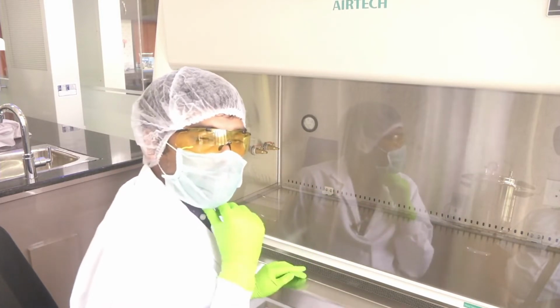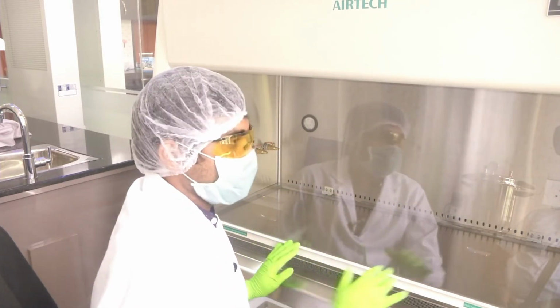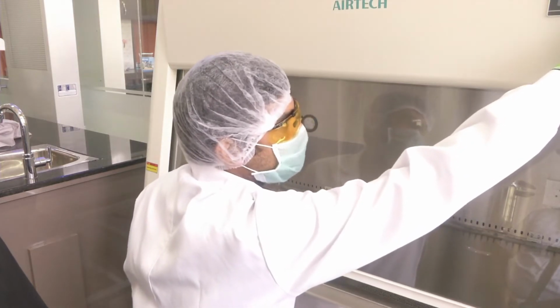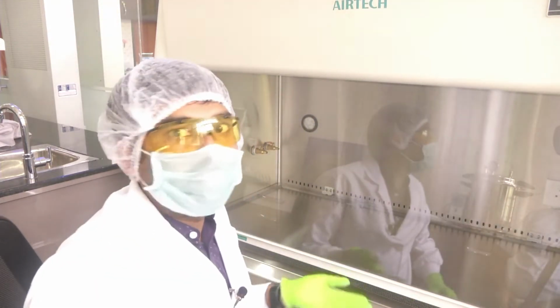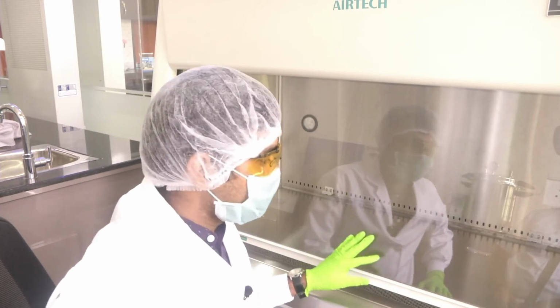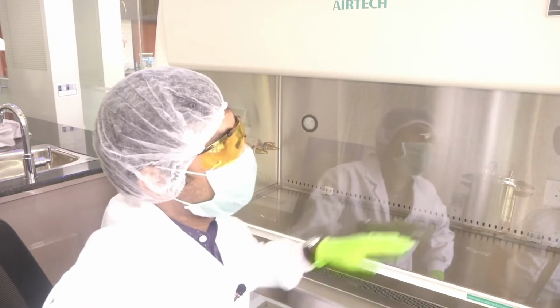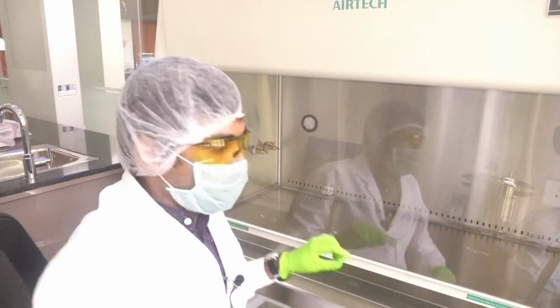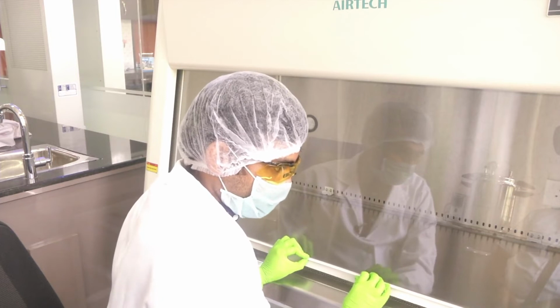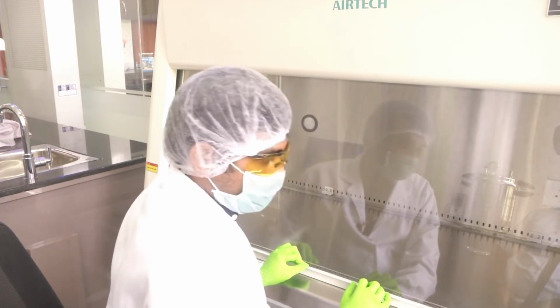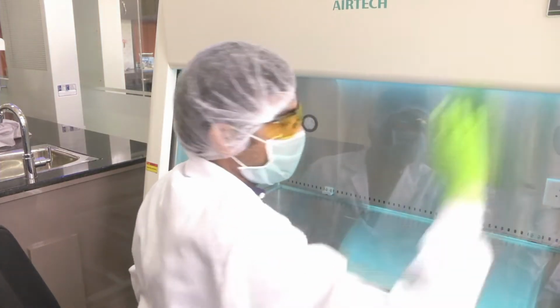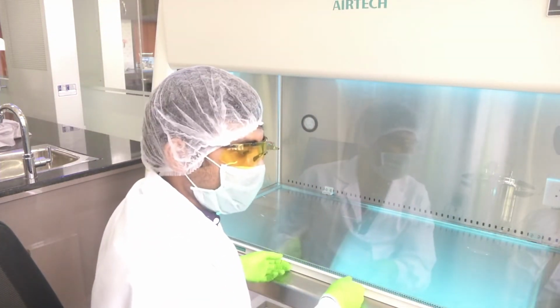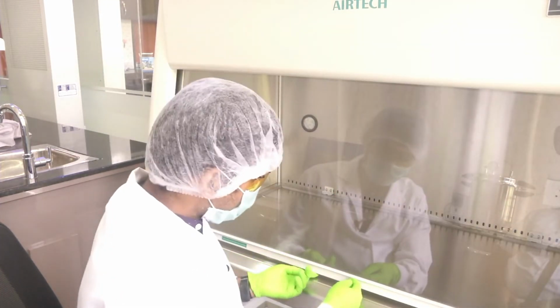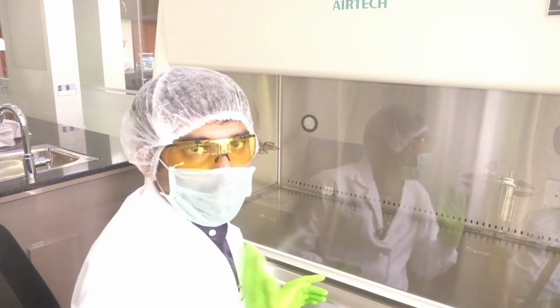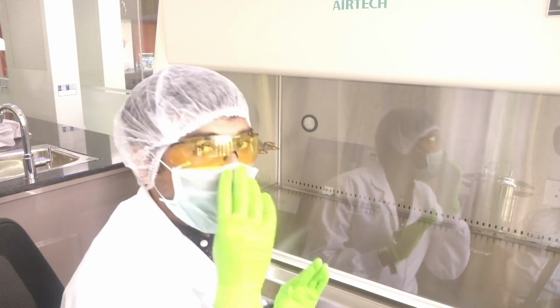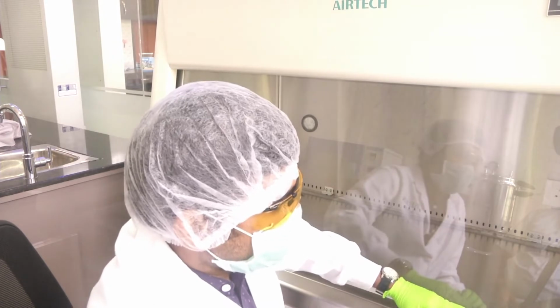Any biosafety cabinet that works in a BSL2 facility will have these features installed. Let us see it again. Let's say I try to switch on the UV light while the lid is up. That equipment will not allow you to switch it on. See, the lid is up right now. This gap is there. I am trying to switch on. It is not switching on. Now I am closing it. Now it's closed. If I switch on, the UV light will come. Let's say we try to open it. The moment it crosses a very small area, the light will switch off. So this is a safety precaution that is provided in case we forget to switch off the UV light.